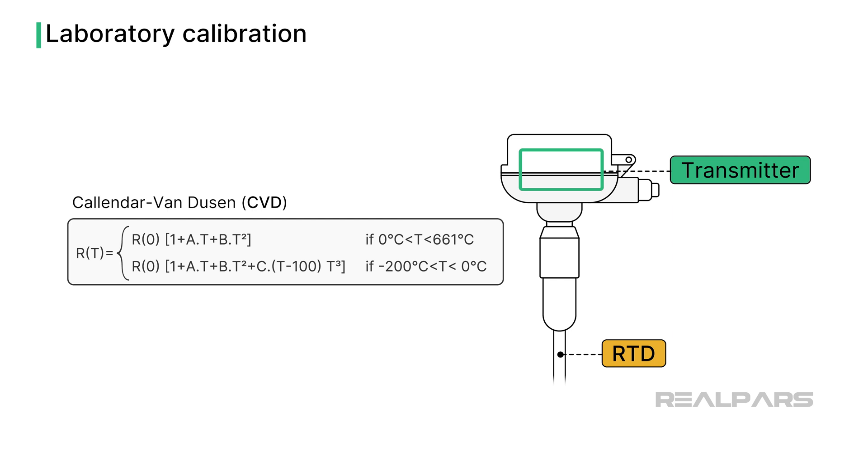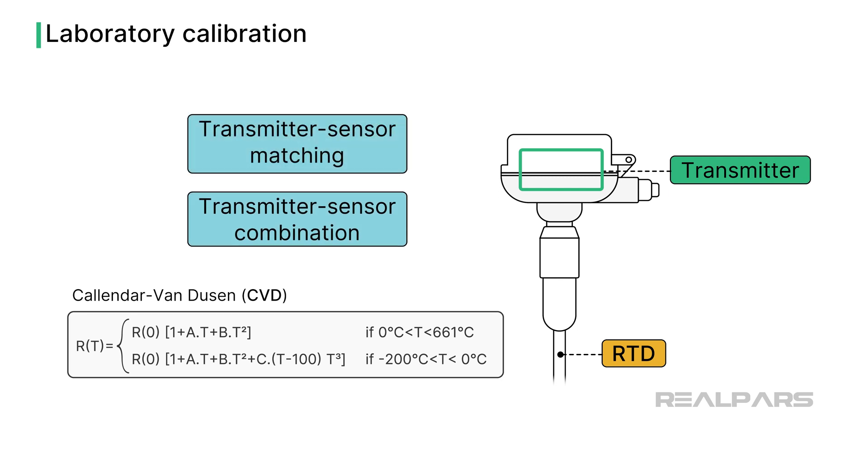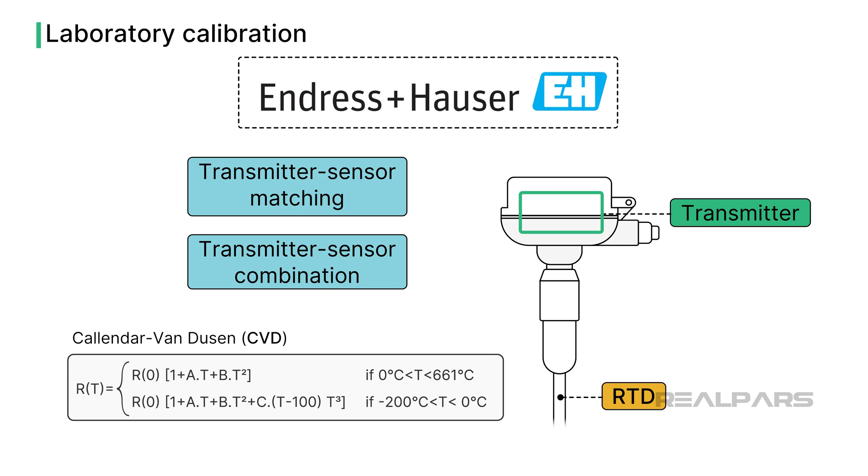Several calibration options are available when purchased as a transmitter-sensor combination, including transmitter-sensor matching using the specific RTD CVD coefficients. Endress and Hauser and several other instrument manufacturers provide such laboratory or factory calibration services.